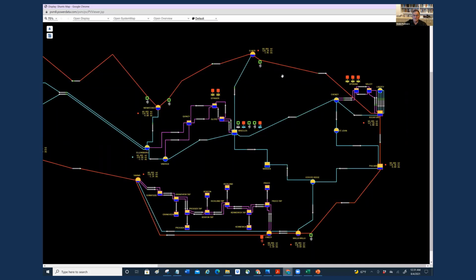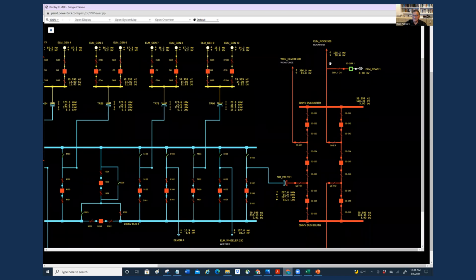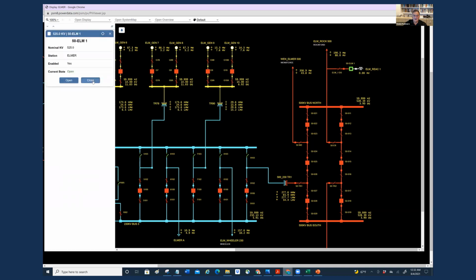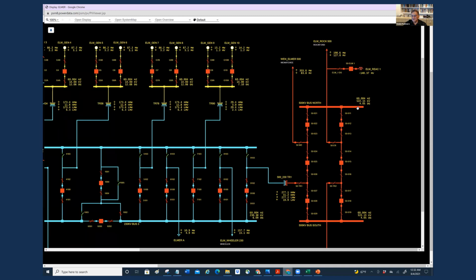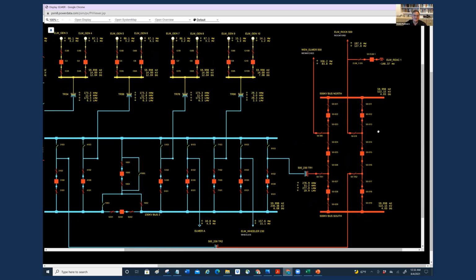So let's go through and actually run through the calculations. Let's calculate the important electrical distances for the Elmer station and at the 500 kV bus. Here's the bus here. We want to look at the impact of switching this reactor into service. Right now we're at 528 kV. And if we close it, we drop to 522. We're getting a 6 kV drop from that. Obviously, if we have a real-time simulator, we don't need to do calculations, all right? But let's imagine we don't have the real-time simulator.